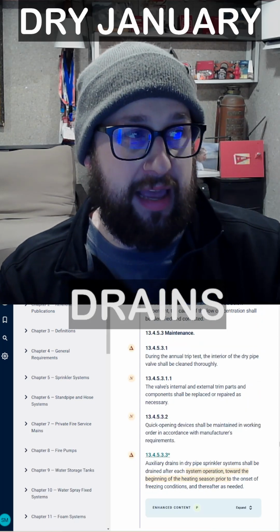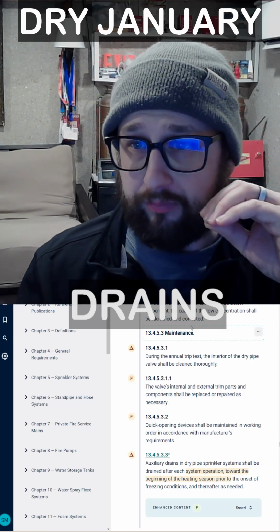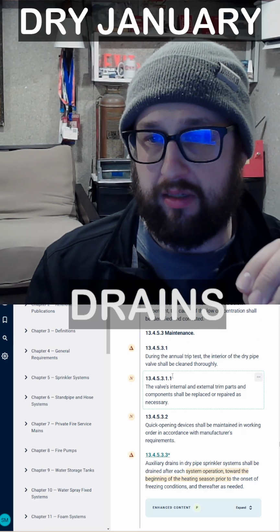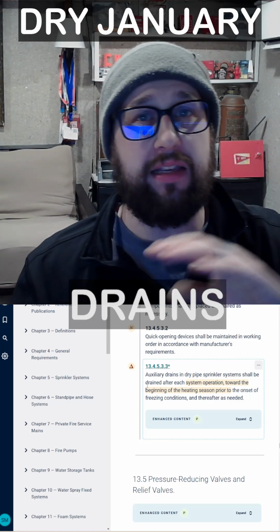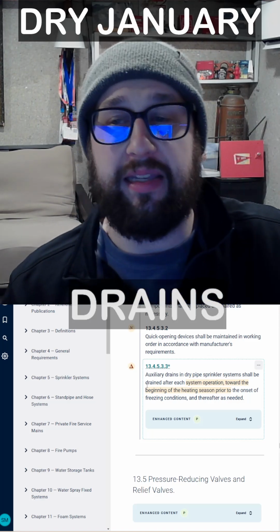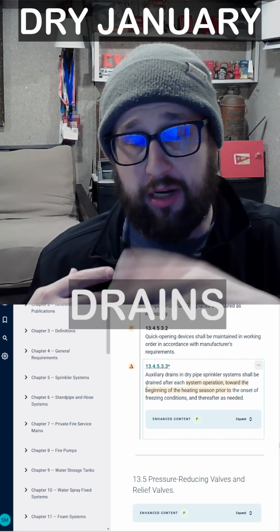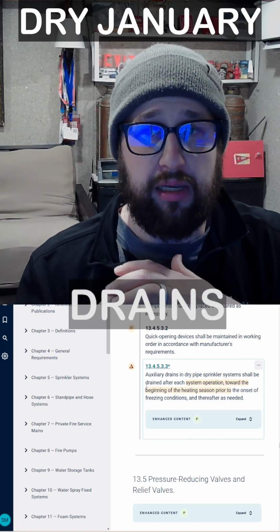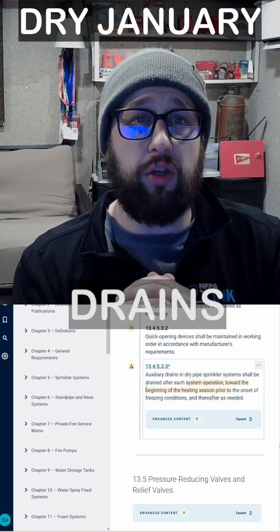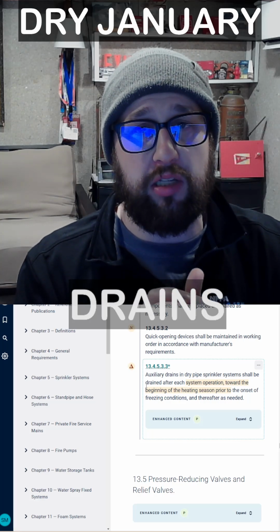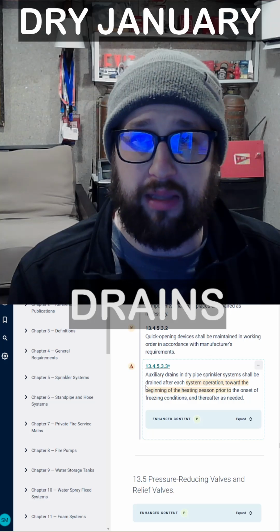Let's go over here into NFPA 25 and look at the maintenance requirements. So what we need to do is, auxiliary drains in a dry pipe system need to be drained after any system operation and then towards the beginning of any heating season. So prior to the onset of freezing, we're going to need to go around and drain those drum drips. And it's an annual thing you need to do before it gets cold. So that's what you need to do as far as installing drum drips and auxiliary drains, and then what you need to do as far as the maintenance to make sure you're constantly drying out that system.